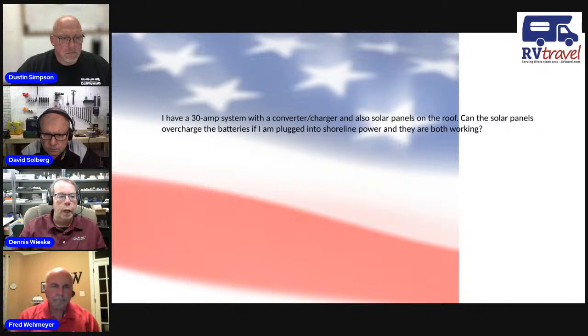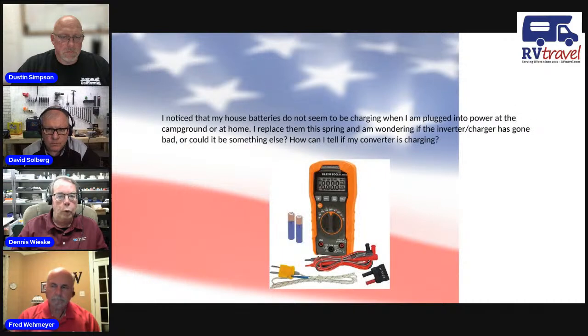The caller mentioned an inverter charger. Those are available - the inverter, when you're on shore power, will also provide charging for the battery. So reading the output voltage on the DC side of the inverter when on shore mode with a voltmeter, you should see voltages of probably 13.6 or higher depending on how the inverter is set up, and you should see that voltage at the battery as well. With an inverter charger, if that wasn't working, it may be a defective charger in the inverter or an open circuit, and of course the inverter would then also not work on battery power.